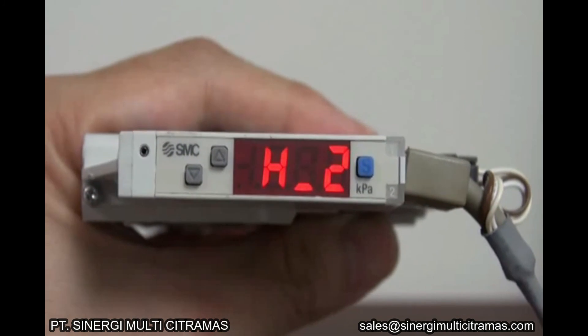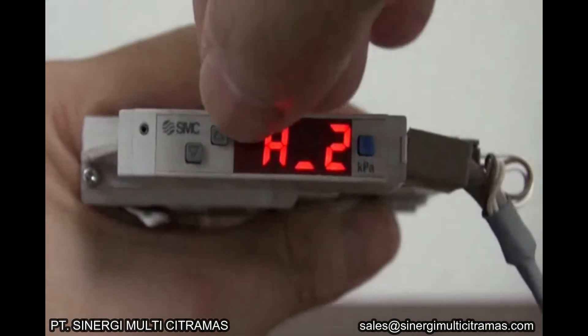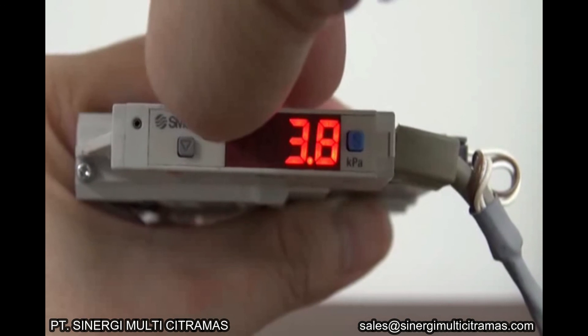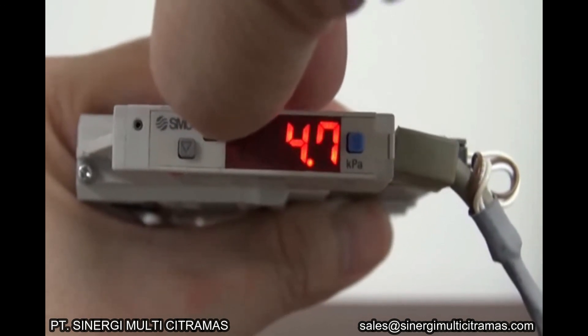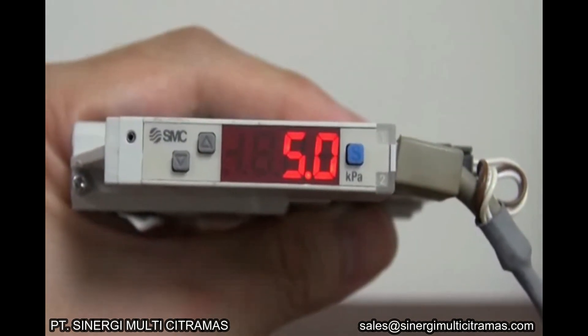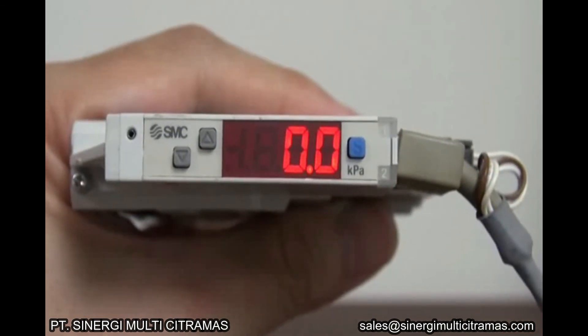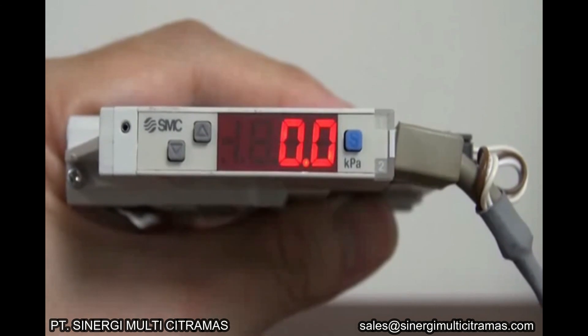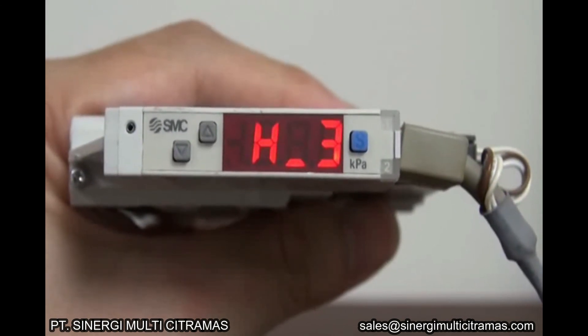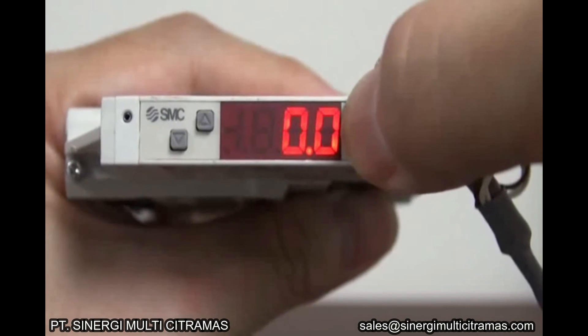In this demo, we shall set the value of H2 to 5 kPa. Press the up button to increase the value. Press the S button to save it. This completes the setting of switch output 2. Press the S button for 2 seconds or more to return to measurement mode.